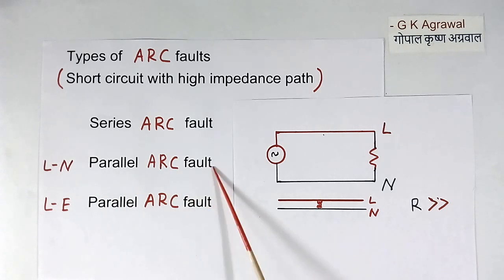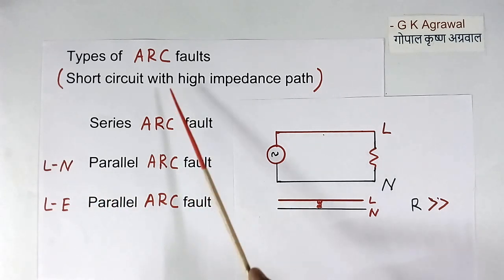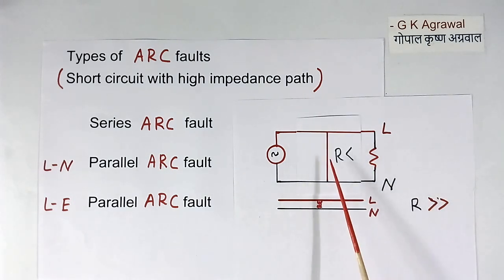Now line to neutral parallel arc fault. This line wire and neutral wire will be running parallel. Distance between these two will be very less. Now suppose here, there is insulation cut or some other problem. Then there will be arcing or sparking. That is called line to neutral parallel arc fault, but this will be high impedance path.